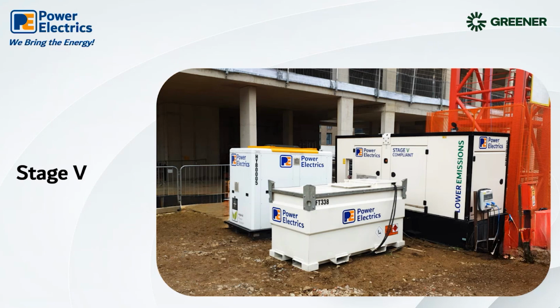Sure, yeah. So, as Sam's just put up the image there, a prime example of stage 5 in the London area alongside batteries and tower cranes. The stage 5 engines, as a lot of us know, need to be run at set loads and high loads to keep the temperatures up for the emissions, etc., to be working. This is where the batteries really come into their own.